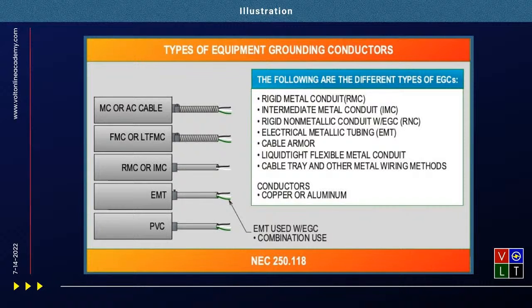If you look at the illustration, just to give an example, if you look at the RMC and the IMC, you'll notice I'm only showing a black and a white conductor. And the reason is because that's all threaded, it ain't going to come loose. I don't know, looks like that arrow's pointed to the wrong thing - no, I'm just kidding, I'm just joking. I have done that before. But it gives you a good example looking at the different wiring methods. We're showing where you'd want to pull that equipment ground in, and showing one where you would take and use the conduit where you feel it's not going to come loose, and that's a good example of it.